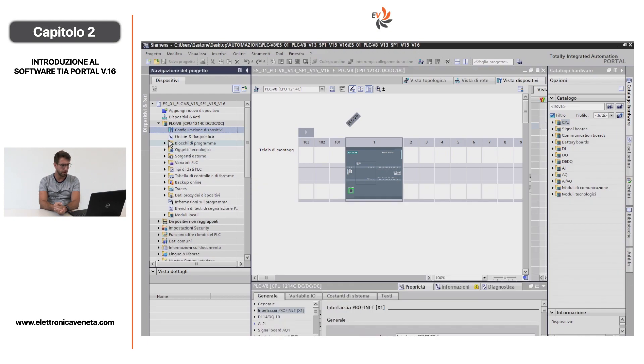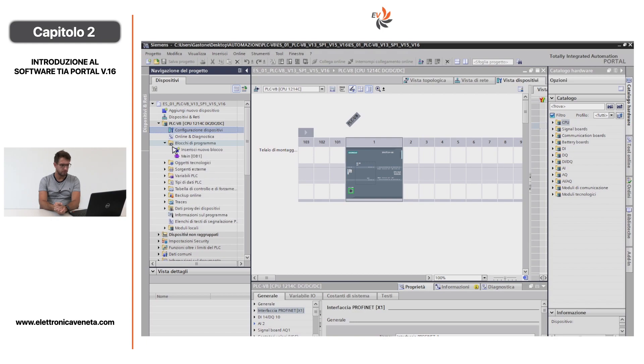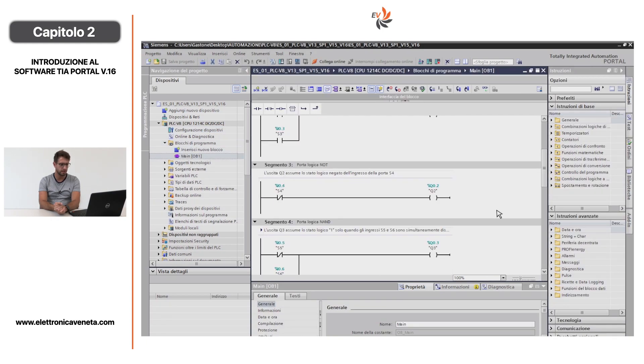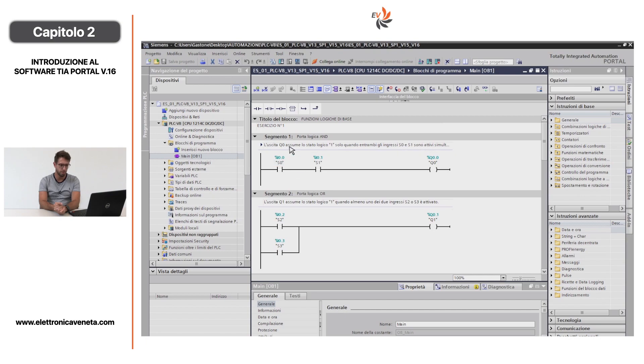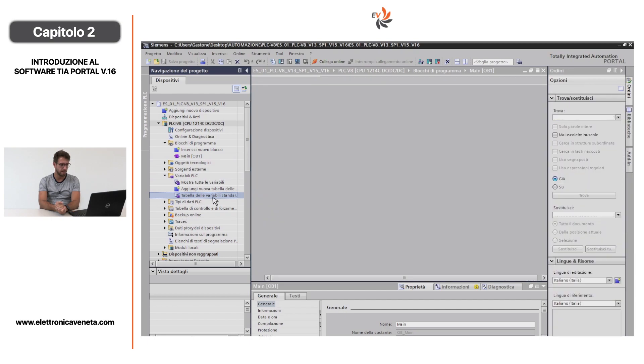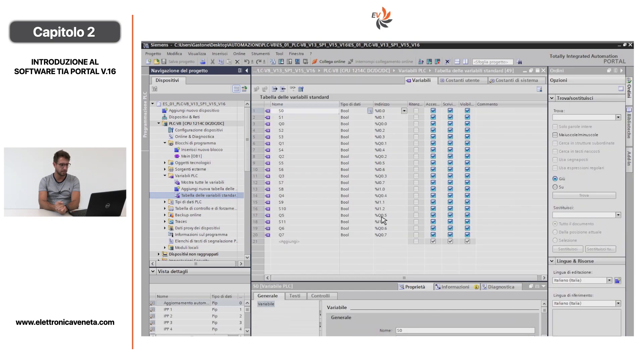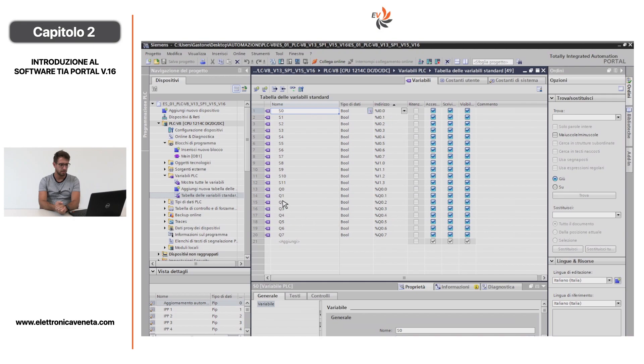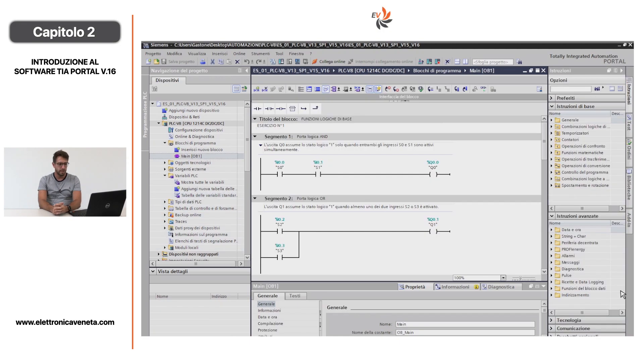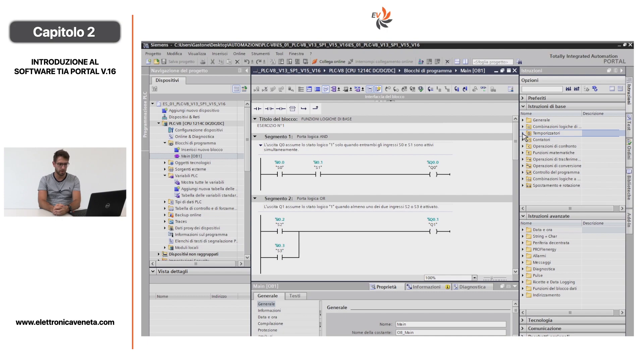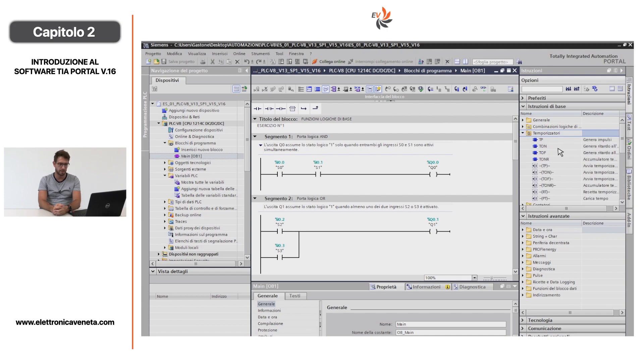Apriamo ora Blocchi di programma. In questo caso si possono trovare i segmenti che compongono il mio programma. Per guardare le variabili si clicca in Tabelle delle variabili standard. Cliccando su Indirizzo si mettono in ordine gli ingressi digitali e le uscite digitali. Per esempio con I0.0 stiamo a identificare l'ingresso S0, mentre con Q0.0 l'uscita digitale Q0. Nell'area di destra abbiamo la possibilità di inserire i blocchi funzione, come le combinazioni logiche, contatto normalmente aperto o contatto normalmente chiuso.